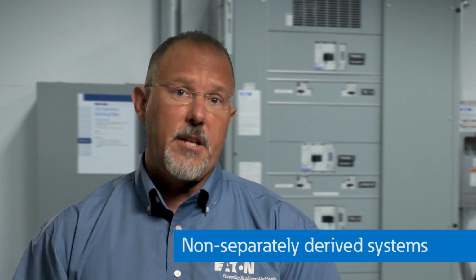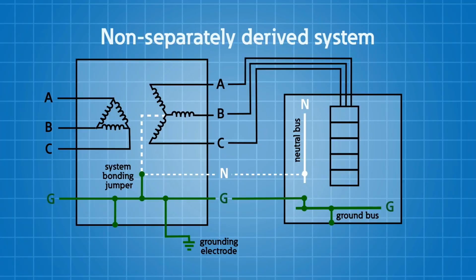Now, we've established what a separately derived system is. And we know that, especially in the case of a generator, depending upon how you bond things in the generator and whether you establish a separately derived system, that will drive the solutions that you purchase and install. Non-separately derived systems, good examples of those are your downstream panel boards, or that generator that doesn't have an established neutral-ground bond in there, where you're using a 3-wire or 3-pole transfer switch. Those are your non-separately derived systems. You're keeping your grounded conductor separate from your equipment grounding conductors in all of those locations.